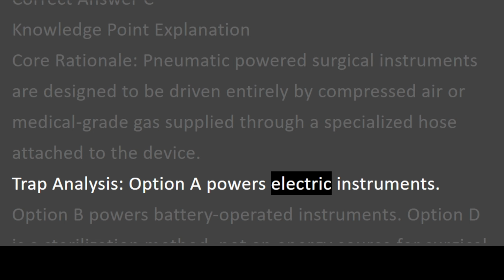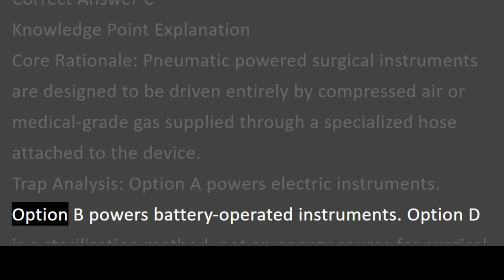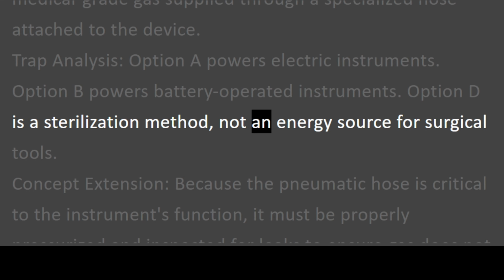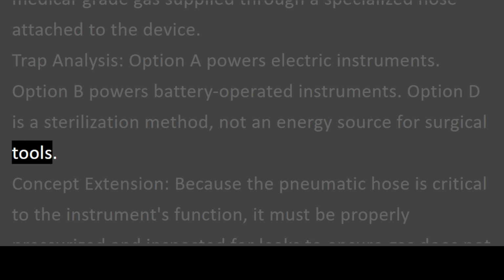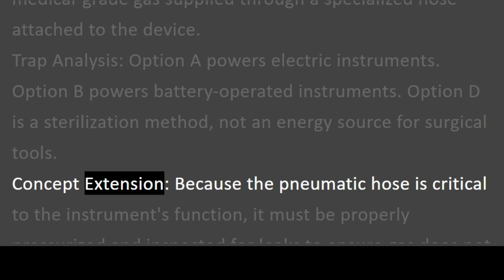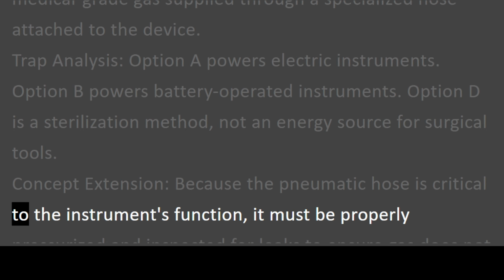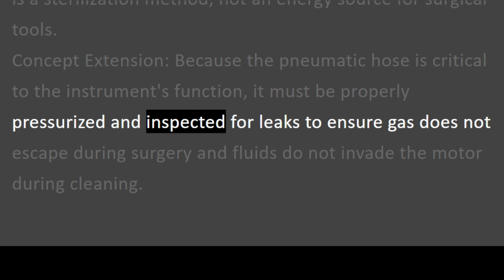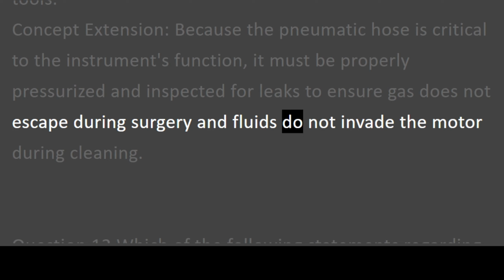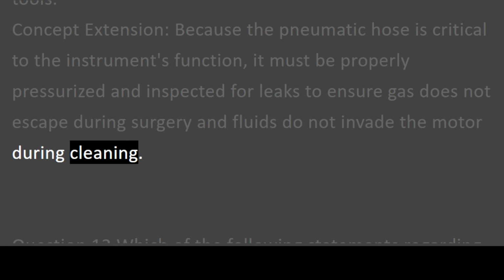Option A powers electric instruments. Option B powers battery-operated instruments. Option D is a sterilization method, not an energy source for surgical tools. Concept extension. Because the pneumatic hose is critical to the instrument's function, it must be properly pressurized and inspected for leaks to ensure gas does not escape during surgery and fluids do not invade the motor during cleaning.